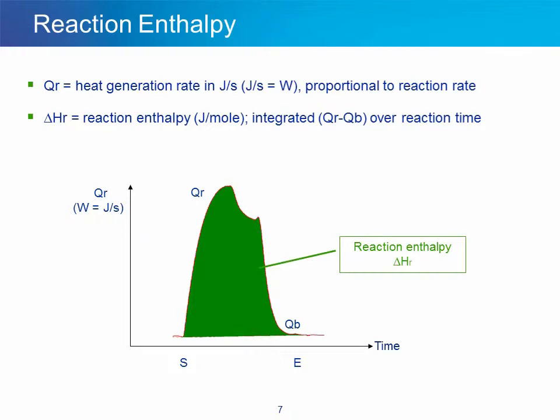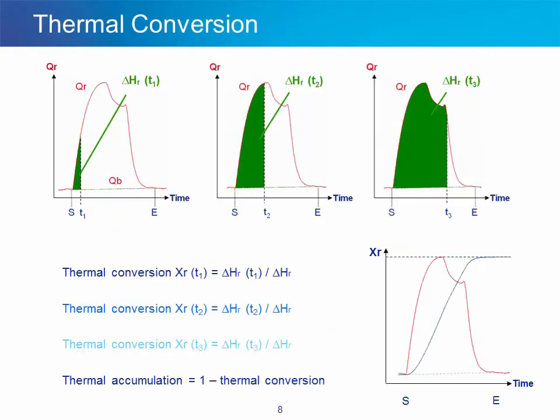Now, if you look at a real heat flow profile like this one, you see time on the x-axis and reaction heat flow, or QR, on the y-axis. QR is actually expressed in watts, which is joule per second. The way you obtain the reaction enthalpy is by looking at the integral of QR over the entire course of the reaction. This gives delta HR, or reaction enthalpy. The software does an iterative integration of the heat flow signal against time, which allows to obtain the thermal conversion profile. This is extremely useful with the Multimax because you can get a preliminary idea of process safety with thermal accumulation data in up to four reactors at the same time.